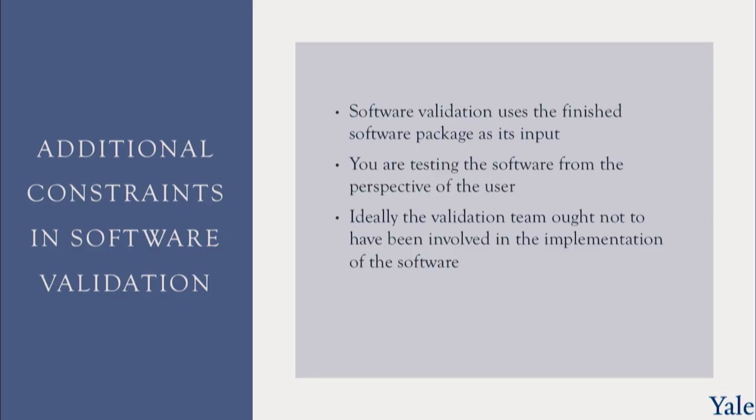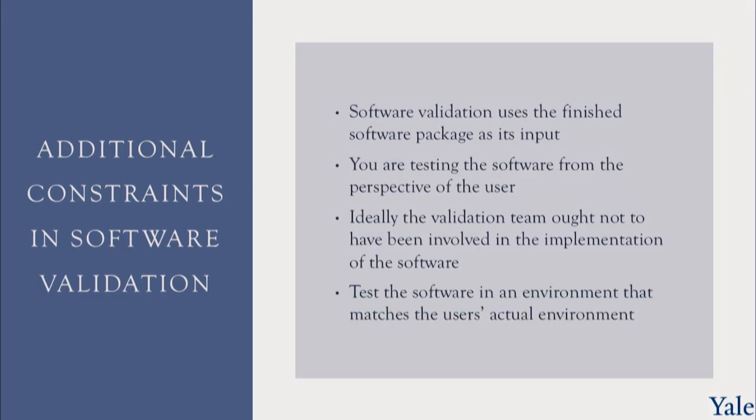And ideally, the validation team, remember we talked about the separation, having a separate validation team, ought not to have been involved in the implementation of the software. These are people who have nothing to gain ideally from that. And we want to test the software in an environment that matches the user's actual environment. Remember here, we're testing the solution, not the code.